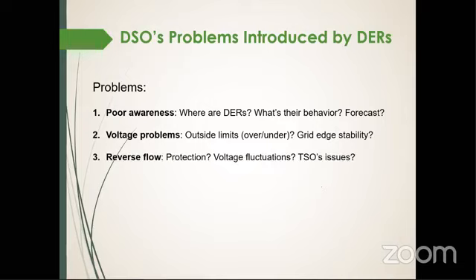Then reverse power flow, the new phenomenon where for the first time in history we have power flowing from distribution to transmission, in periods of light load and high production of renewables. This can cause protection problems, voltage fluctuations, and even problems for TSOs. So DSOs need to be aware and able to prevent it.